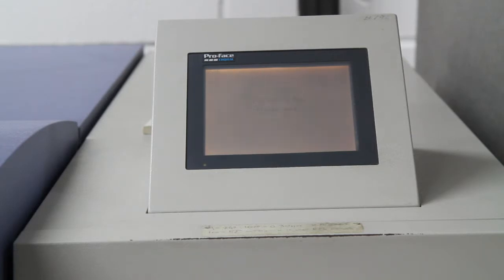So if the power's drifting down, when you do a laser calibration, it pulls it back up again to 270. So you're internally calibrating this. You're not calibrating the RIP. It's nothing to do with the RIP. So the way you work is you calibrate this first, then you calibrate the RIP, which you did like linearization. Job done again.